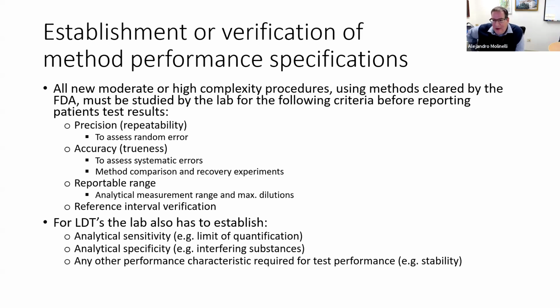When it gets to your lab, you don't just put it in the instrument and start running it. You still have to verify that the performance matches what the manufacturer says as to precision, accuracy, reportable range, reference interval verification. If you have a lab developed test, instead of verifying the performance, you have to establish the performance parameters. So you have to do the same experiments, but to establish the performance. You also have to add a few more things: analytical sensitivity, specificity, and this is the big one, any other performance characteristic required for test performance, for example, stability, any other thing.